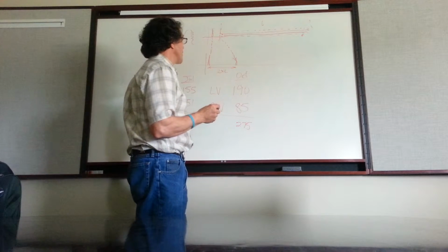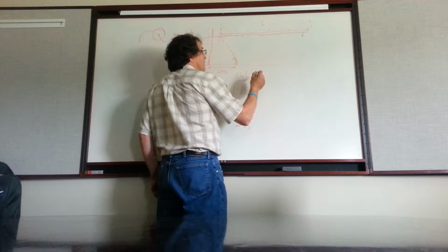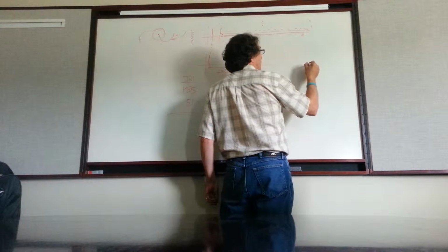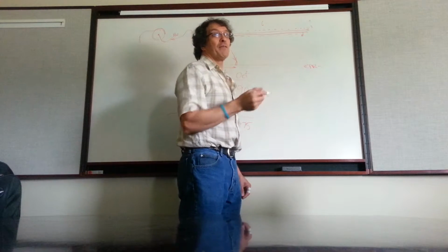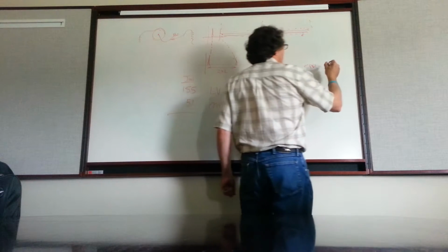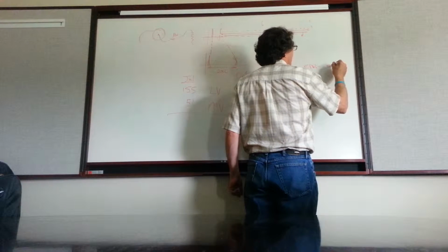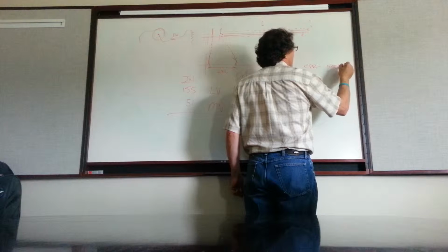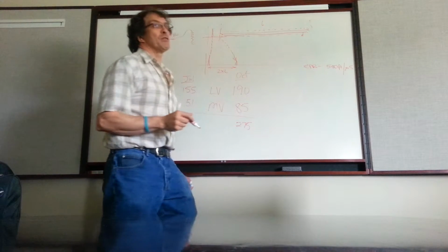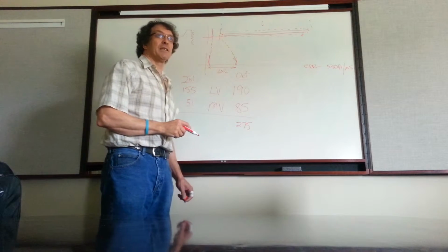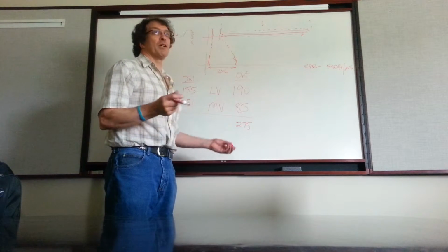Now the number they give us for EPR, the number we were coming up with for the speed that it's travelling through the cable, was something like 540 feet per microsecond. So every microsecond the pulse is travelling 540 feet. So if you know the distance between them, you can work it out in time.